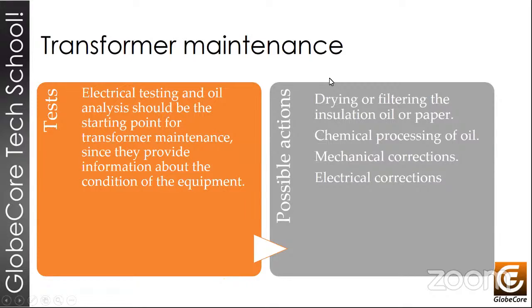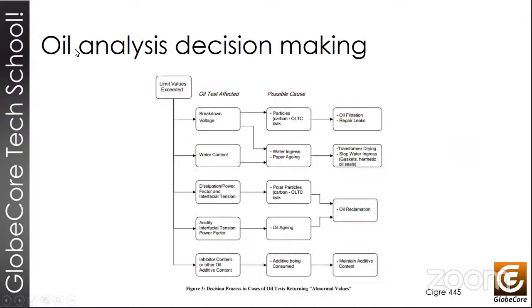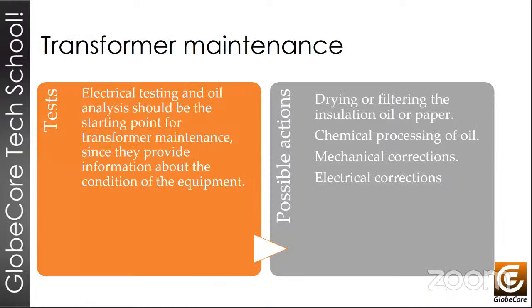So now that we have this information, we can perform various actions, and we'll need to, for example, filter the oil or dry the insulation paper, etc., based on the information we gather. We may need to chemically treat the oil. We may need to add an inhibitor or a passivator, even regenerate the oil. We may need to do mechanical corrections, such as improving the physical connections. It may be that we find leaks in the transformer, problems with gaskets or problems with insulators, etc. And all of these problems must be corrected.